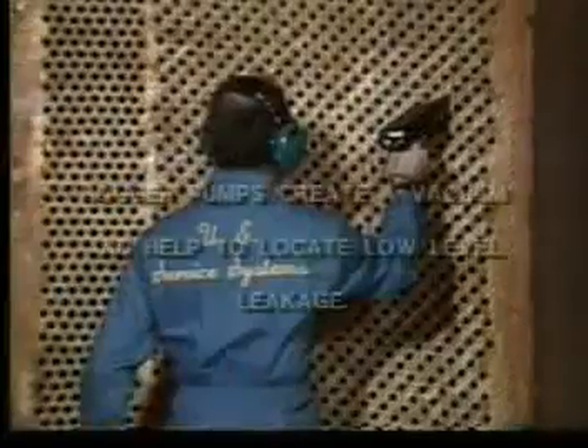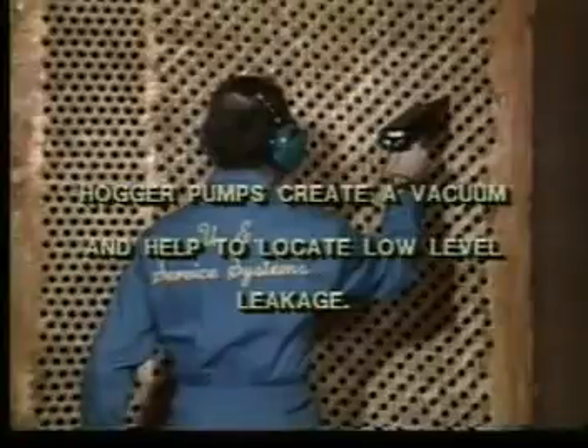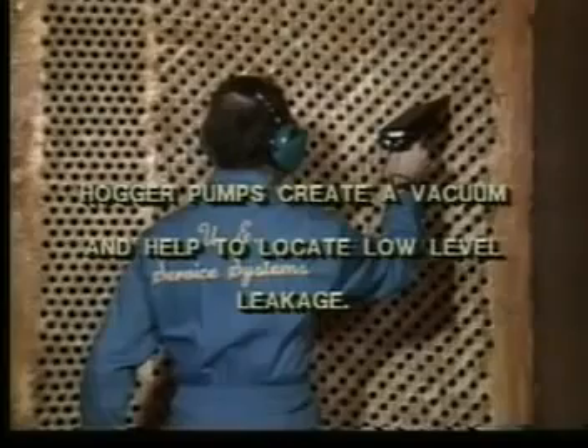One last technique for locating a leak site should be mentioned. It is highly effective, but can only be conducted during an outage. Use Hogger pumps to generate a large vacuum on the steam side. Then scan inside the inlet and outlet tube sheets for leak sounds.